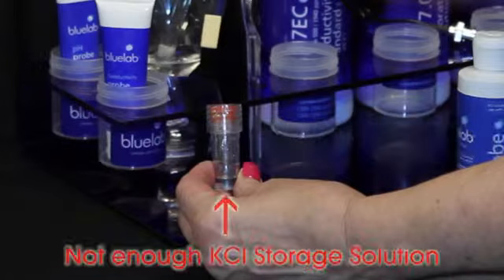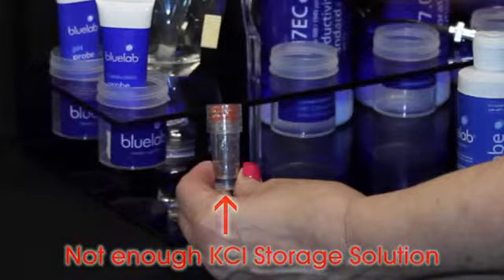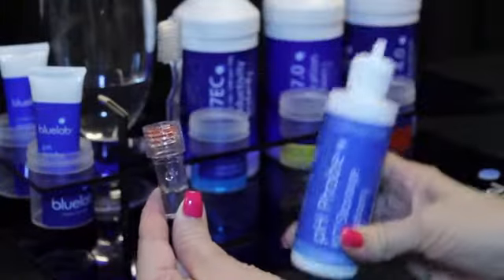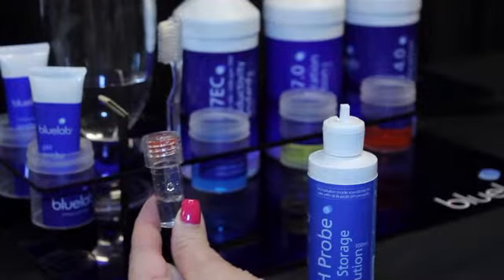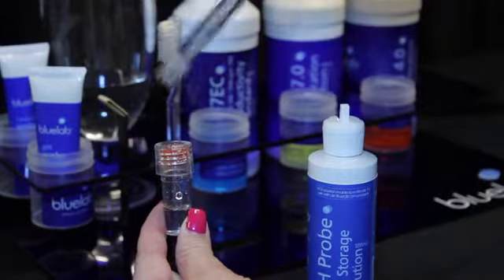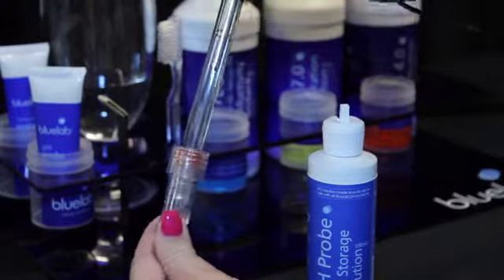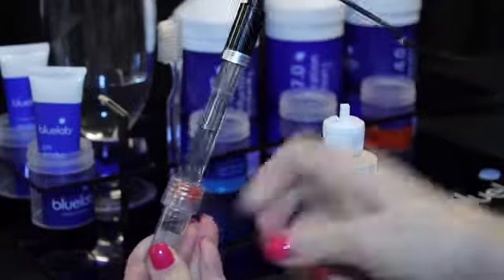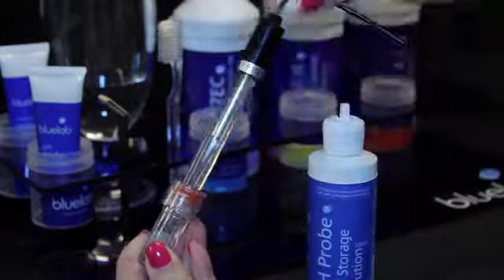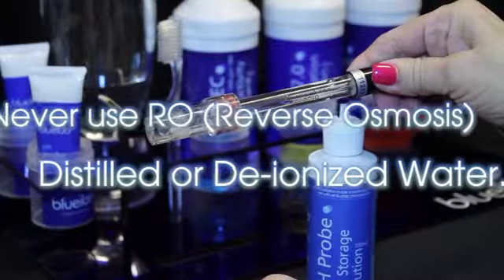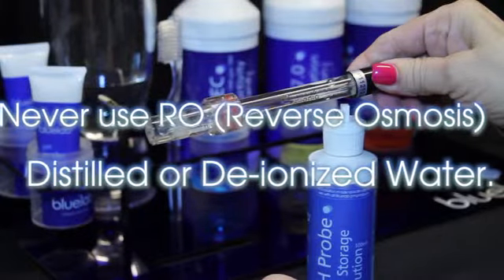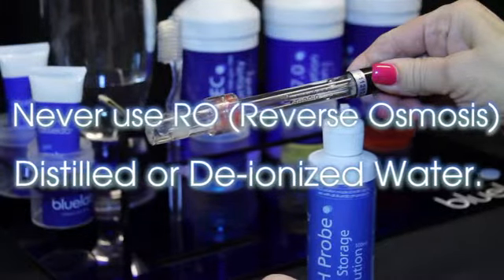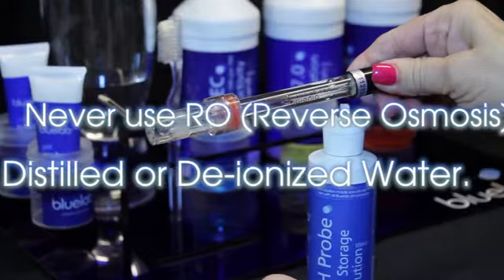Check there is enough Bluelab pH probe KCl storage solution in the cap to cover the probe tip. If not, add KCl solution to ensure the probe tip will be covered. Place the cap back on the probe, twist the top counterclockwise to secure. Always store the pH probe in KCl storage solution. Never use RO, distilled, or deionized water. Pure water changes the chemistry in the probe, causing the probe to die.